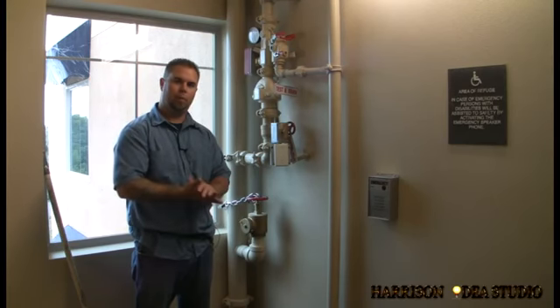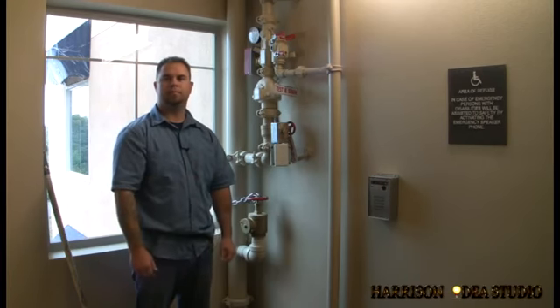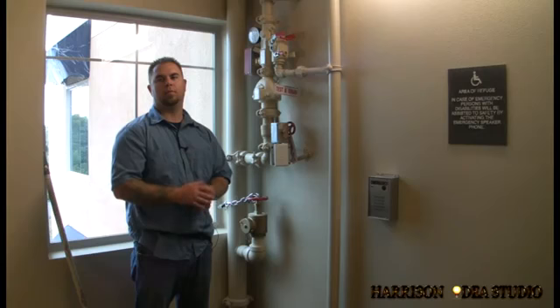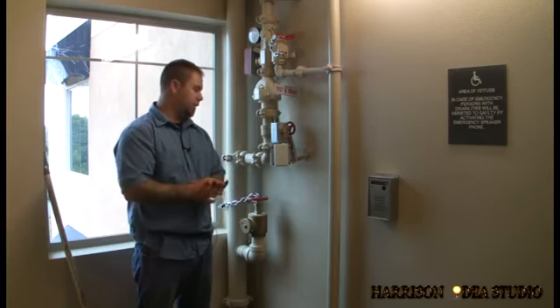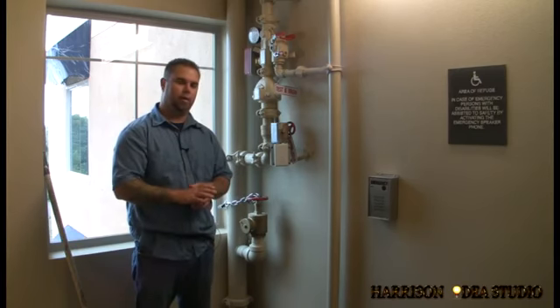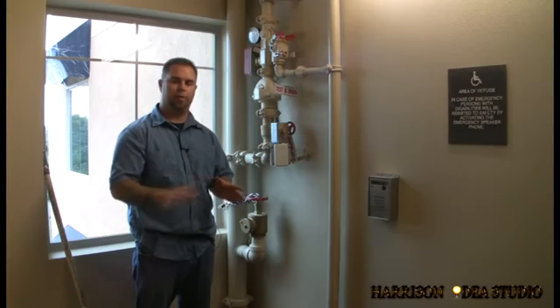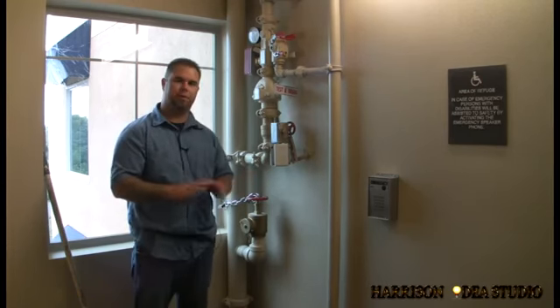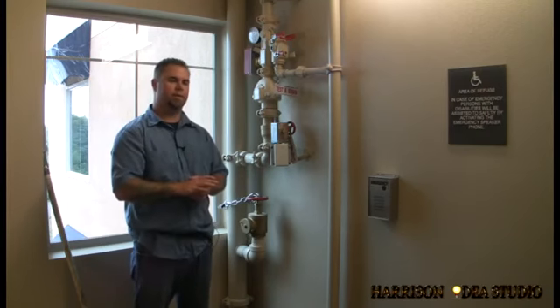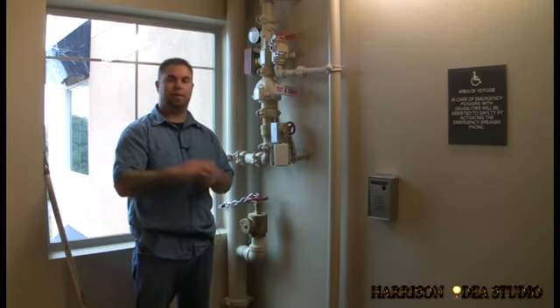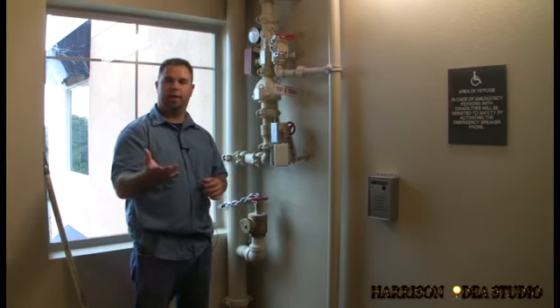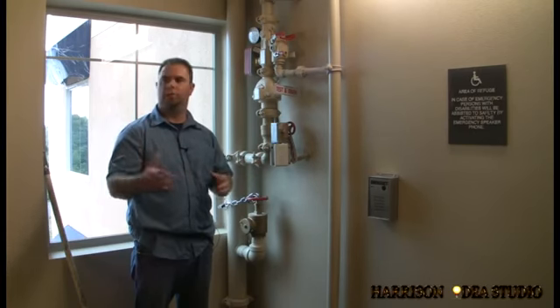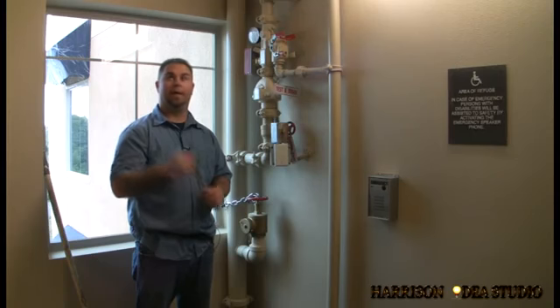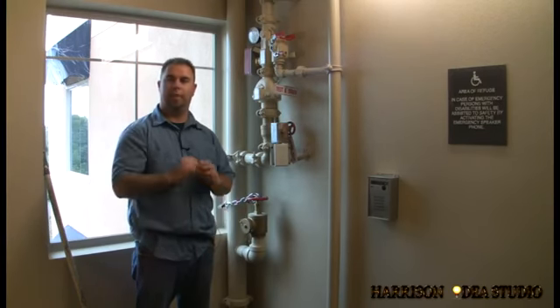And is there any reason for the facility people here at the site to ever be doing anything to the system? Integrity's recommendation is to not have anybody at the facility, as far as maintenance or management goes, to touch the fire sprinkler system really in any way, unless there is an emergency where somebody accidentally breaks a sprinkler head, kids are playing in the rooms, or somebody decides to hang something from a sprinkler head and it pops.